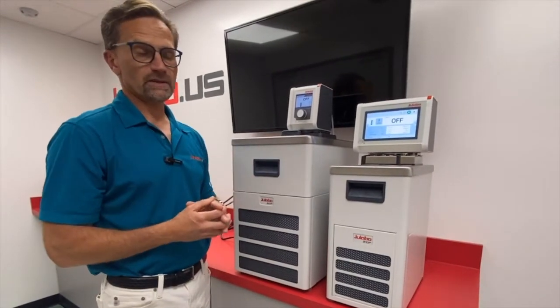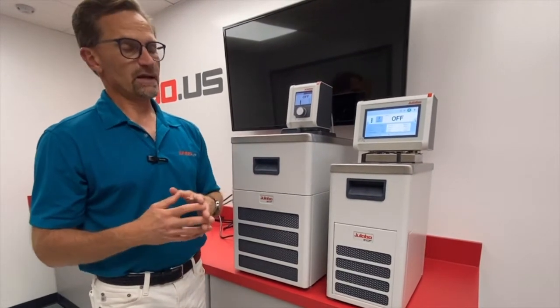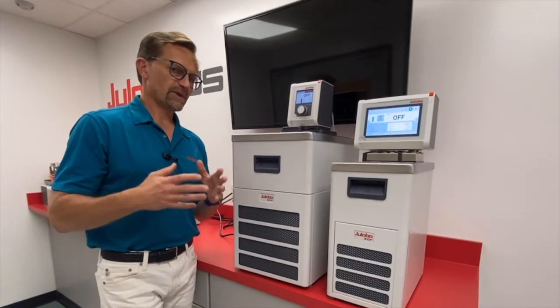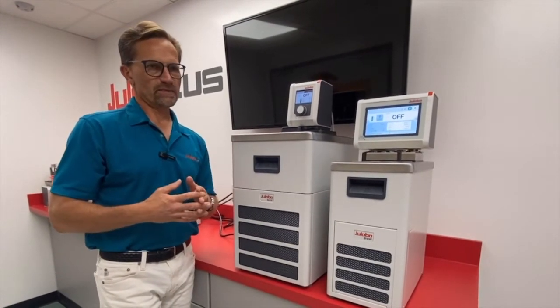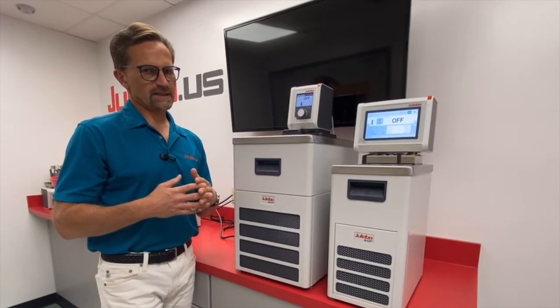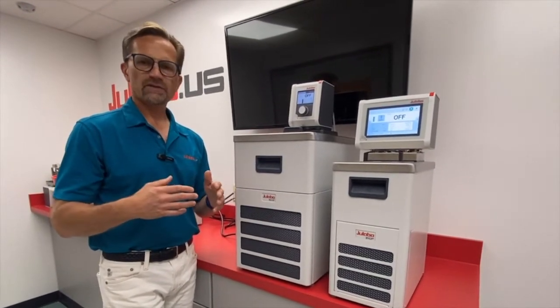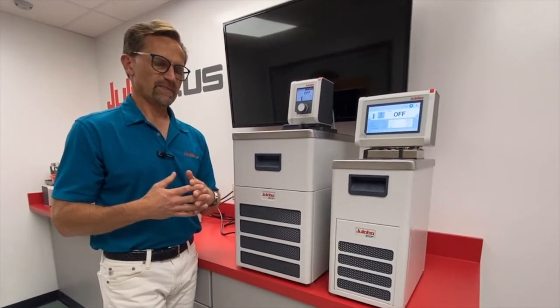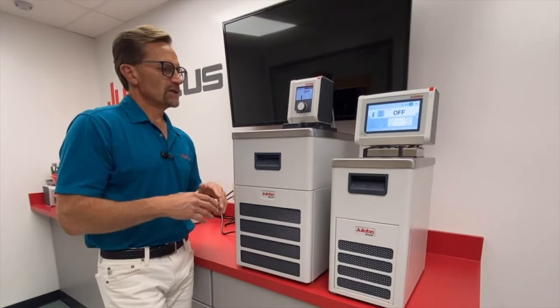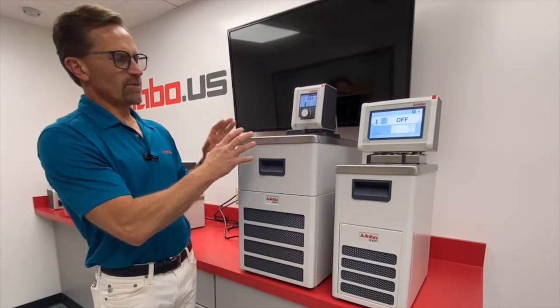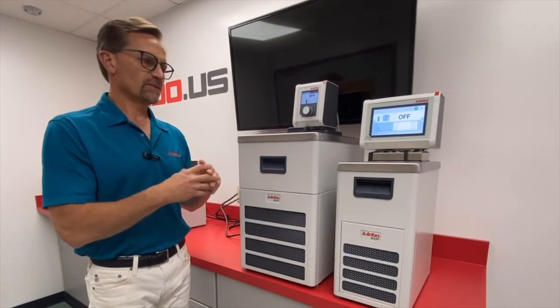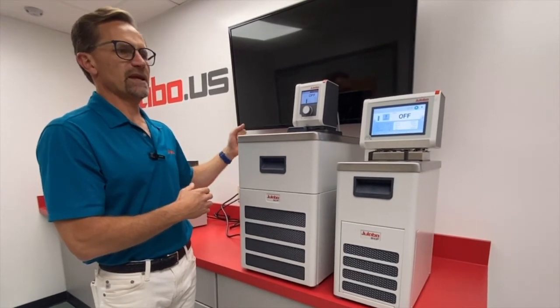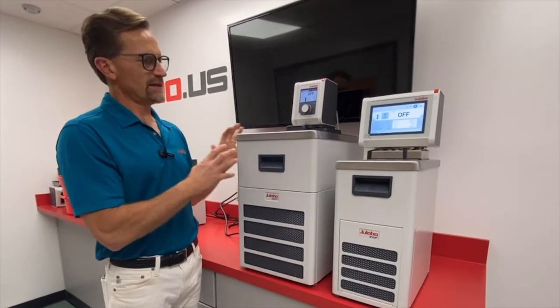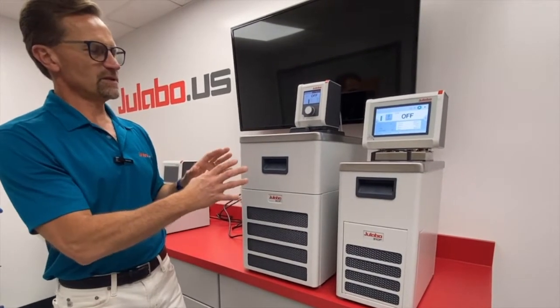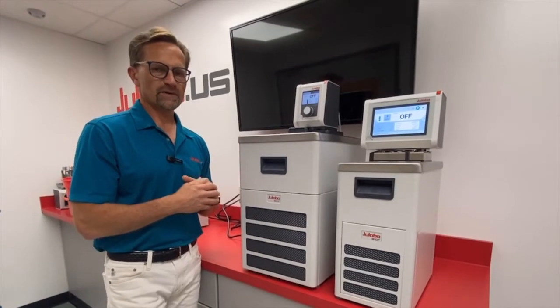The pump on the MAGIO models, in comparison, is a pressure suction pump. It is adjustable electronically only, but it has a lot higher pressure and flow rate capability than the DYNEO pump. So it has the capability of doing 16 to 31 liters per minute with pressure values of 3.5 to 13.3 psi. Okay. So both units incorporate external PT100 capability, which is important for ensuring that your application is at the temperature you want it. And that really is the key feature of both of these model series, to have that PT100 sensor capability.